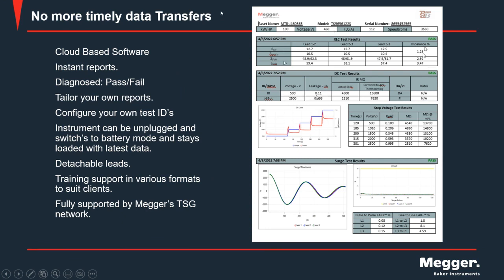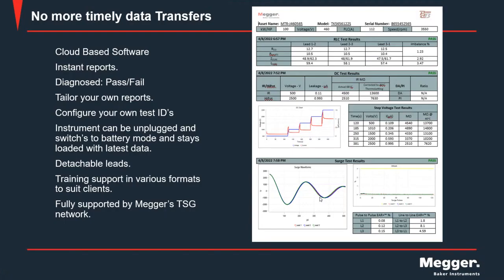Then we've got our insulation resistance, our high pot, our polarization index, our step voltage test or our high pot test, and then we've got our surge. And if we did a PD test, we could add that value. So that gives us a summary of the test equipment that we now have in the ADX, which is our latest instrument to be released recently.